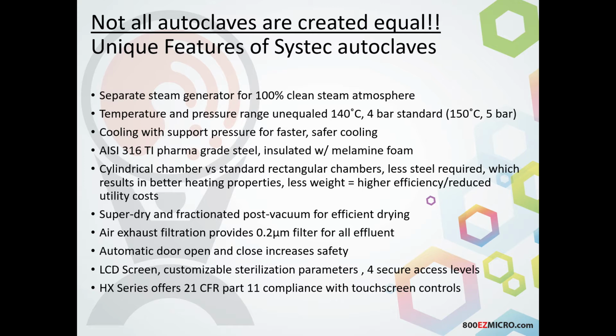So we do offer a super dry and fractionated post vacuum for efficient drying. So we will dry everything inside of the unit completely at the end. Even if you were to put laboratory coats or something like that inside of the autoclave to be sterilized, we have a programmable drying time that would allow you to program and dry everything completely, especially for things like pipette tip boxes and other items that you don't want to have secondary contamination coming from by unloading a wet item from the autoclave and placing it on the bench.